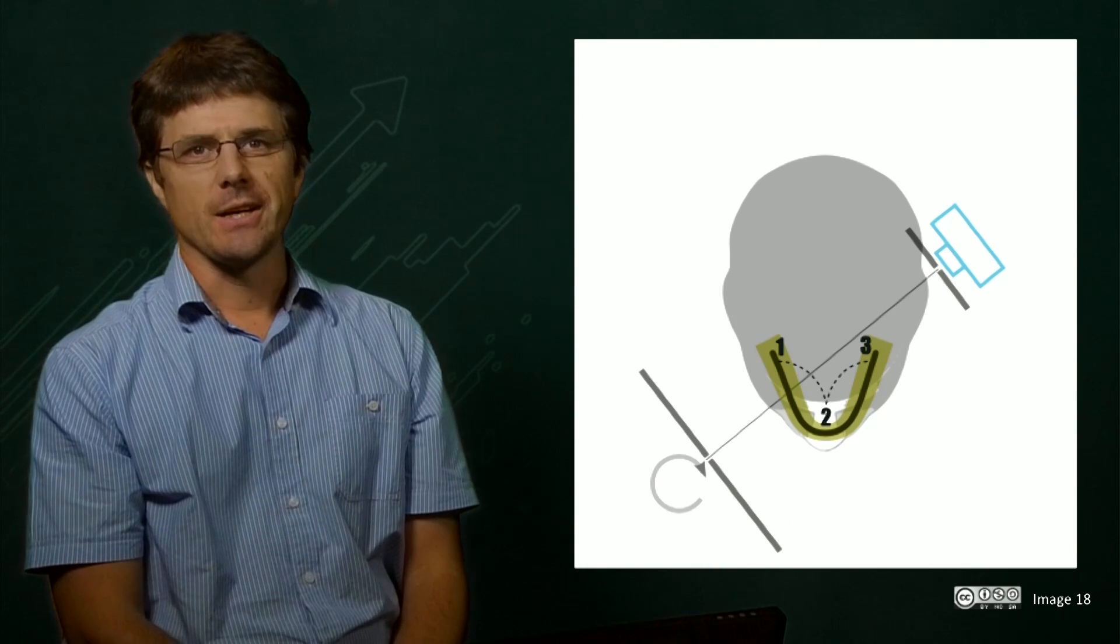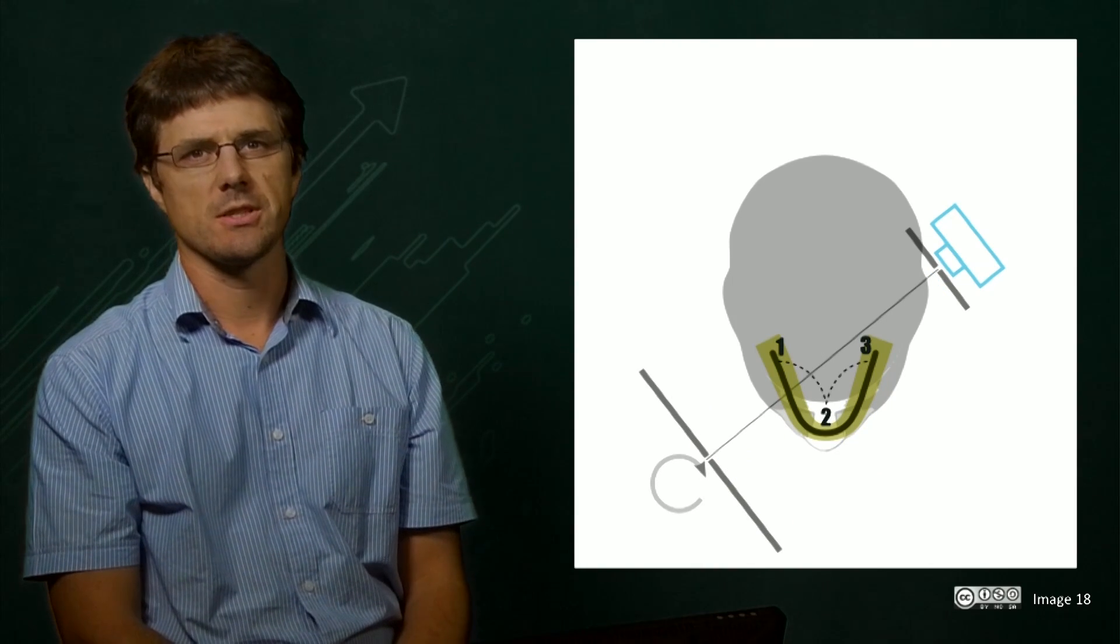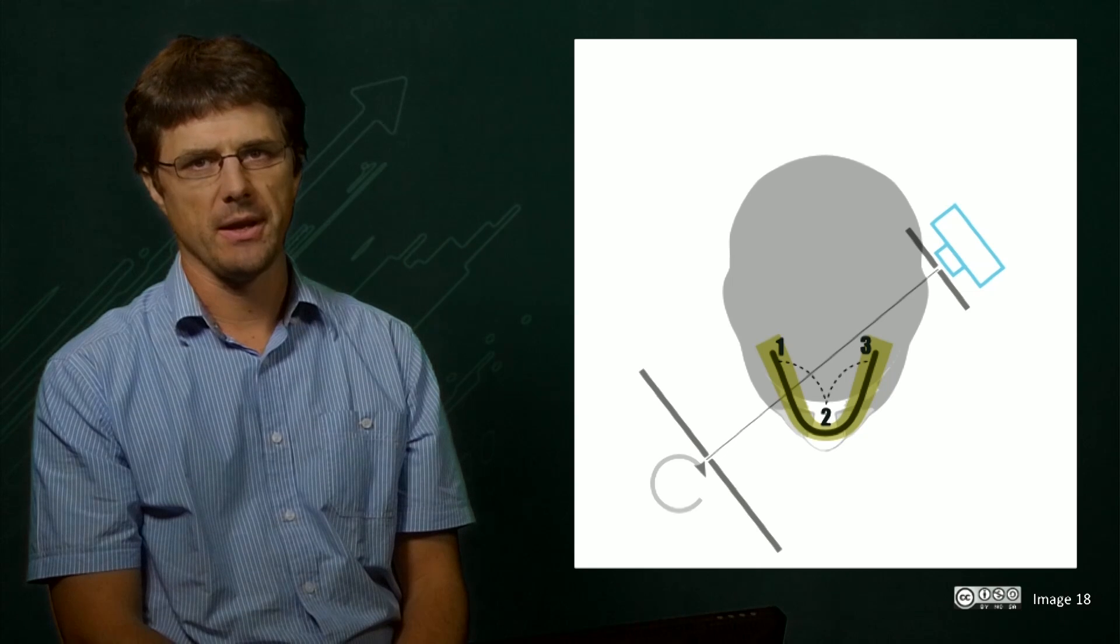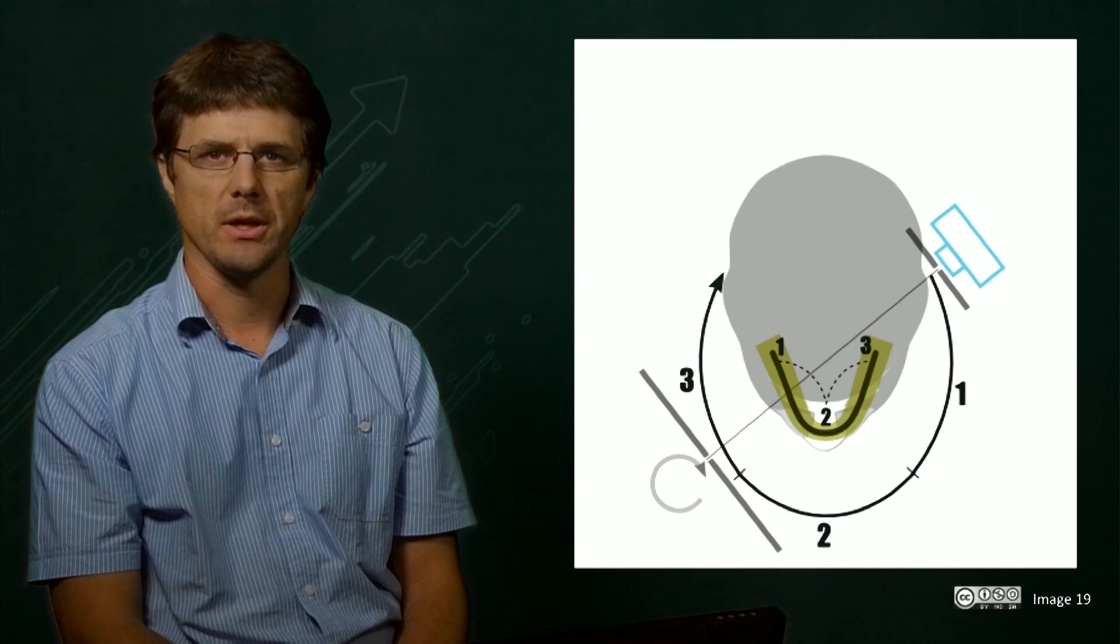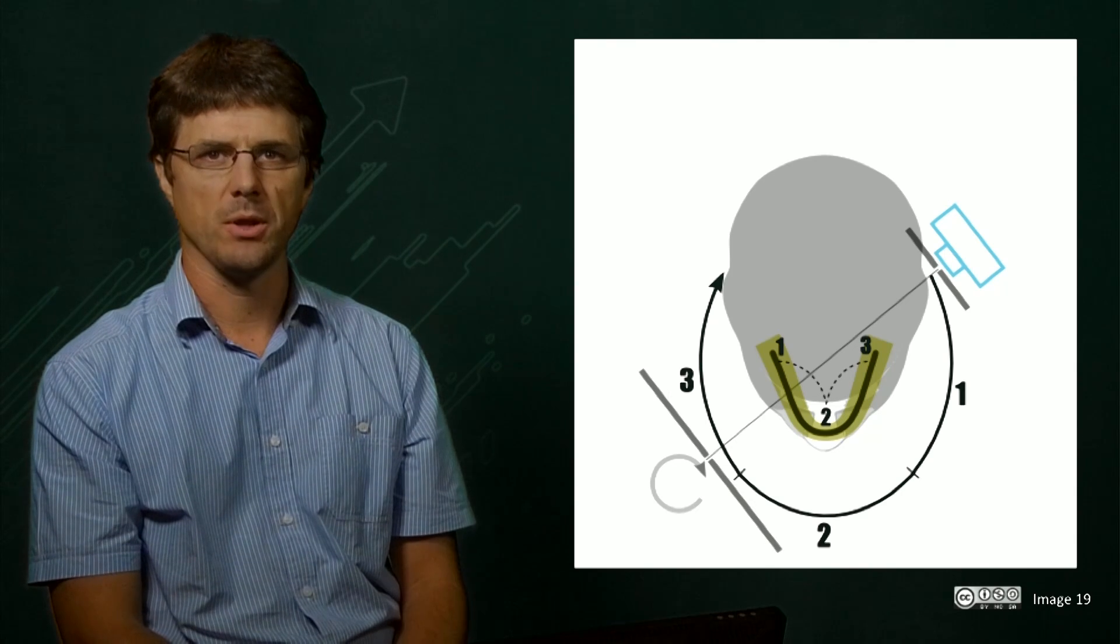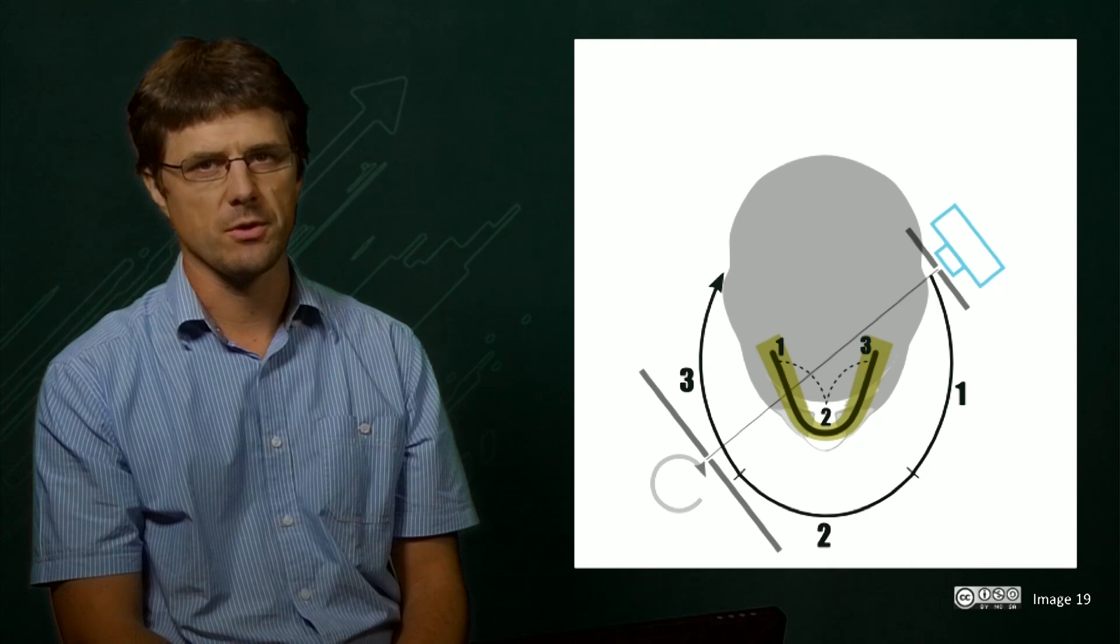In order to better fit this arch, some manufacturers use a sliding centre of rotation for the main arm that shifts between three points. The net result is a curved imaging plane that changes in width as the plane will now vary in distance from the camera.